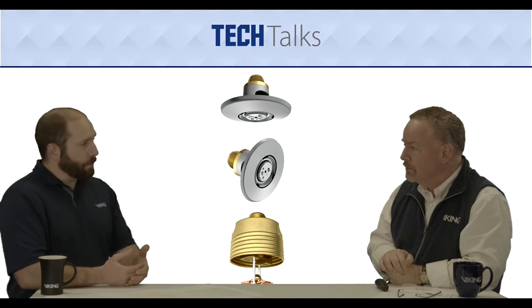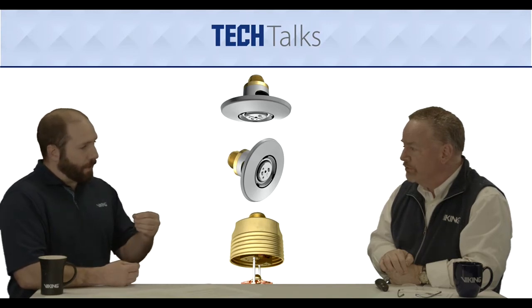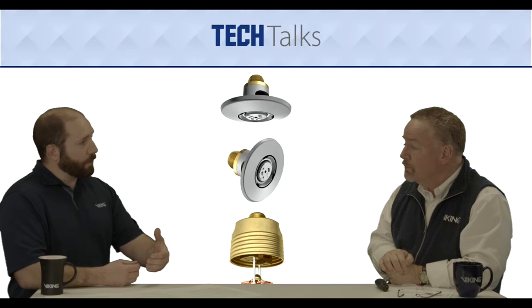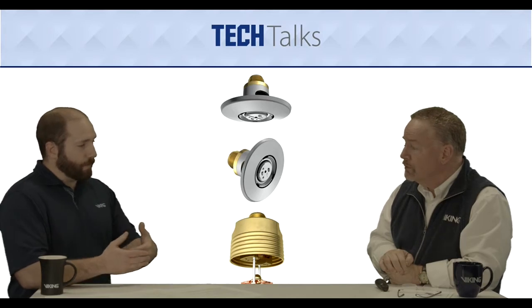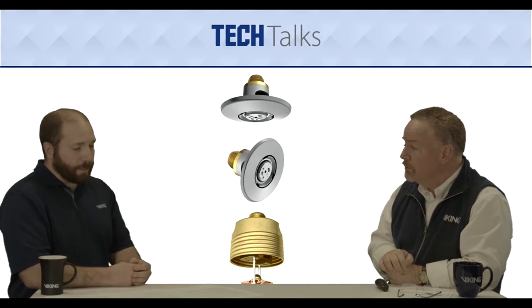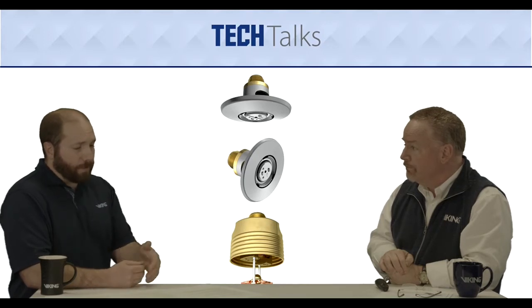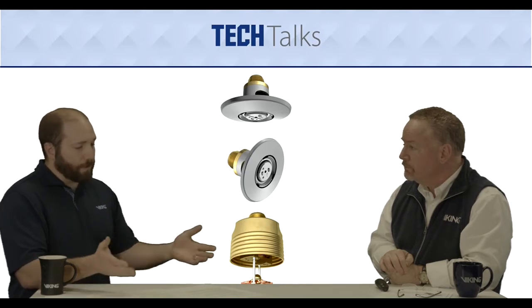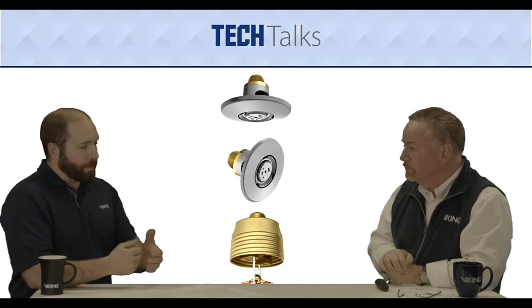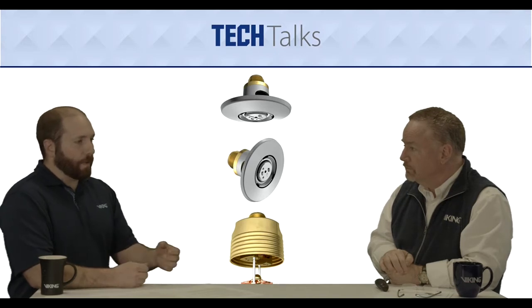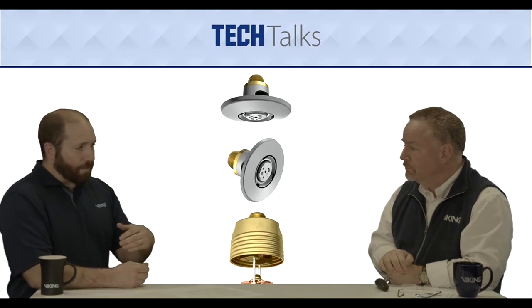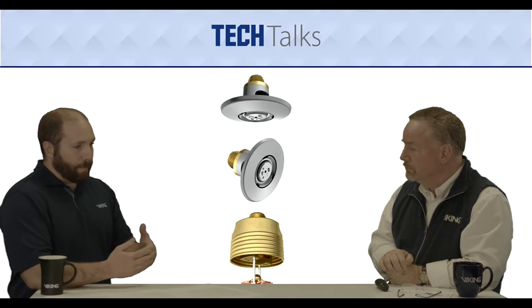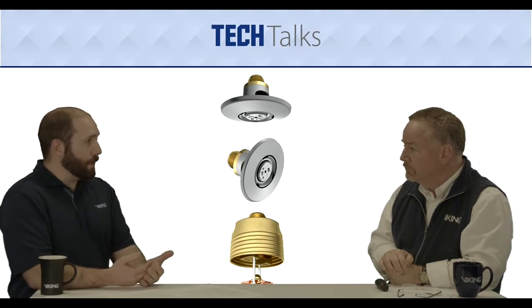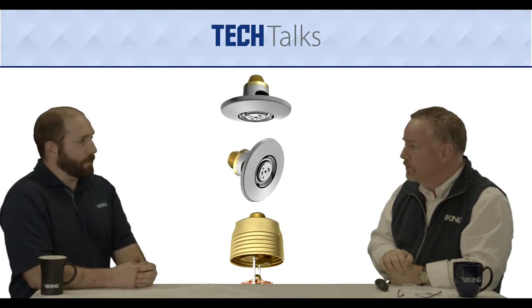It's still going to be per the actual UL 199 testing for a standard spray sprinkler or an extended coverage sprinkler. It's going to go through all those same tests. The only thing that's really special about it is how it's marketed. It's more of a tamper resistant type of assembly, but it's really just a standard spray sprinkler.